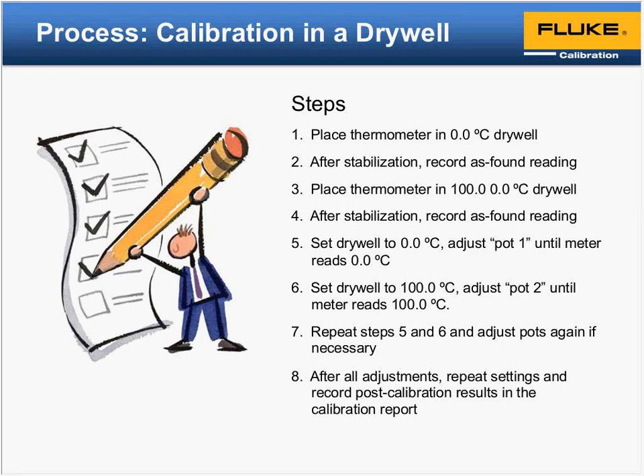One thing to note that we touched on in the last slide is the probe and the drywell. That's trying to complicate the situation, trying to get everything immersed at the same depth, basically in the heat source. Not on the slides, but something to make sure you do is immerse to the top. Again, in a cold unit, you're going to see the temperature change the closer or further away you get from being fully immersed in the unit.